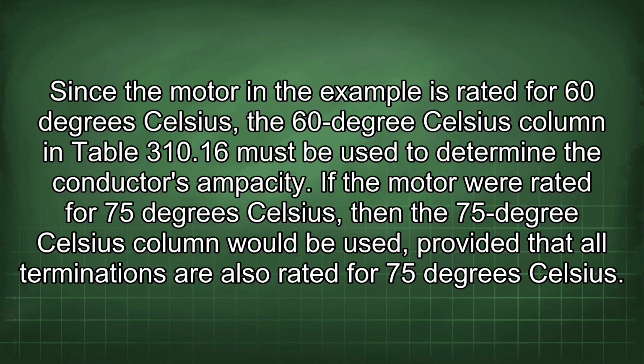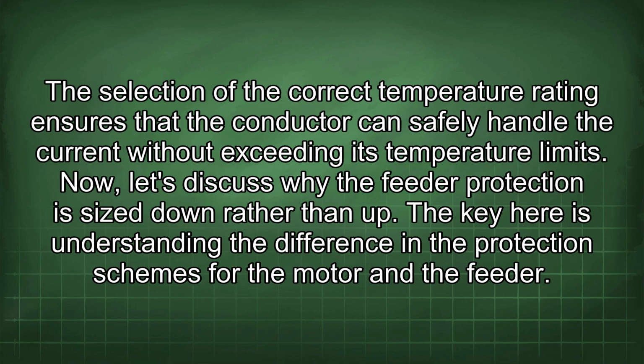If the motor were rated for 75 degrees Celsius, then the 75 degrees Celsius column would be used, provided that all terminations are also rated for 75 degrees Celsius. The selection of the correct temperature rating ensures that the conductor can safely handle the current without exceeding its temperature limits. Now, let's discuss why the feeder protection is sized down rather than up.